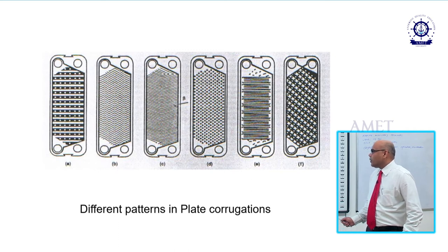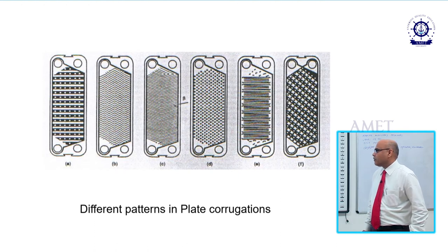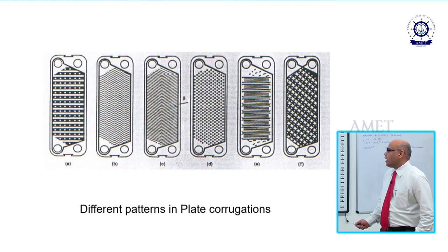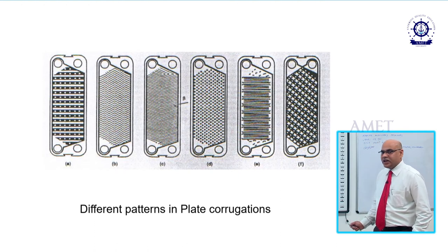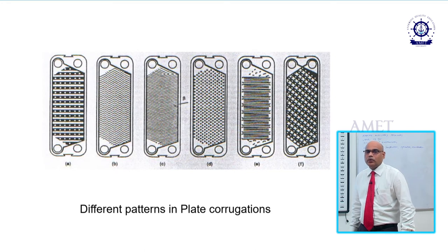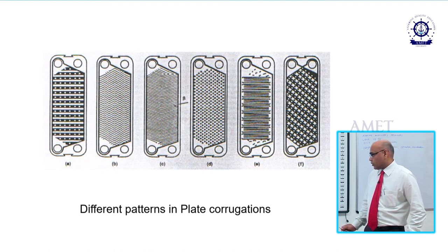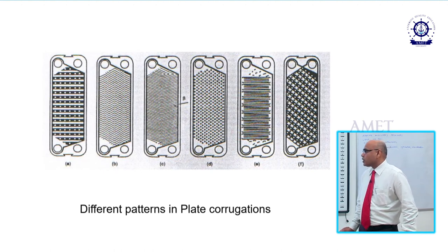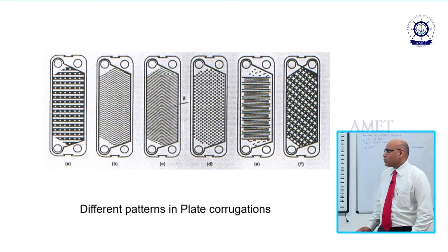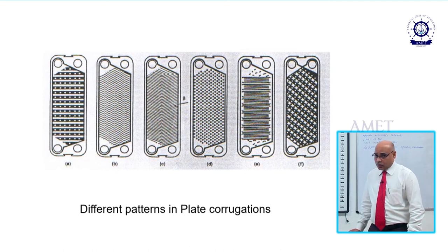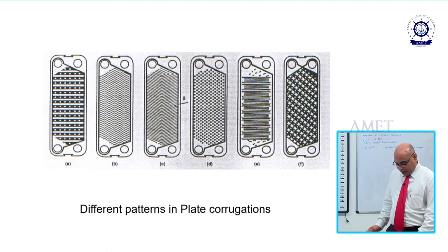The corrugations also promote turbulent flow, which further increases heat transfer, and they give additional strength to the plate to withstand high pressures. Because of this, the plates are corrugated. However, one must remember the plates are very expensive, so their shape has to be taken care of.